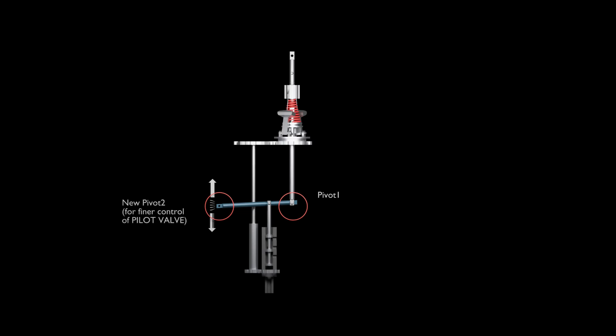So it is evident from above, pilot valve directly taking feedback from the rotating flyweights alone cannot give a stable operation. We need to give another feedback to the pilot valve of a different kind, simultaneously for its positioning, which can take care of this transient lag. This feedback must have two characteristics. One, the feed to the pilot valve must cover the time lag or gap between the instantaneous fuel rack reading and the engine RPM during power piston travel while increasing or decreasing fuel. It must be able to bring the pilot valve that extra bit closer to cover the control port in advance before the lag period lapses.